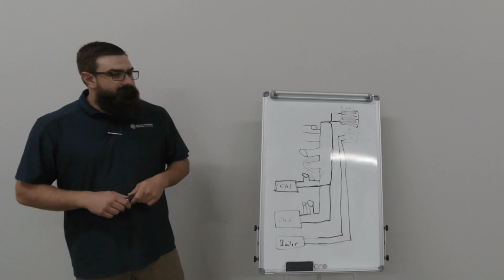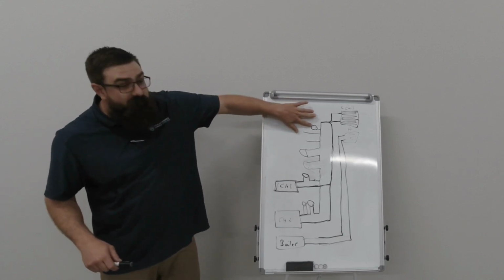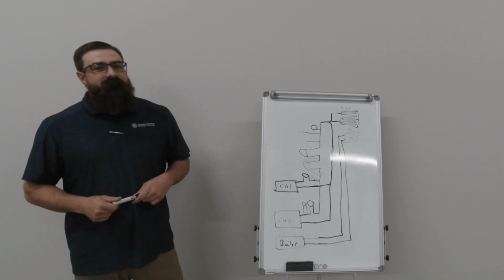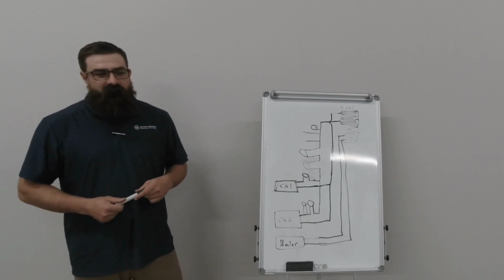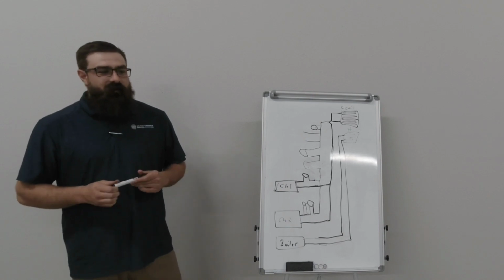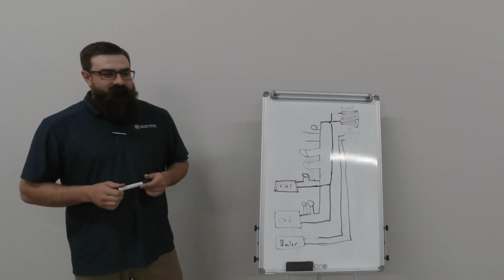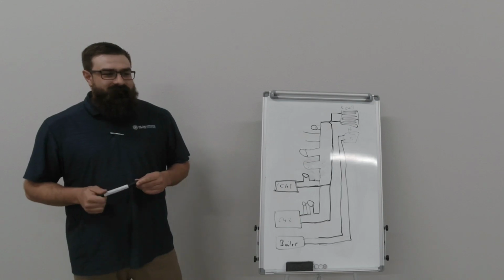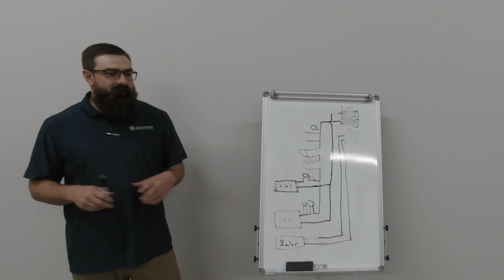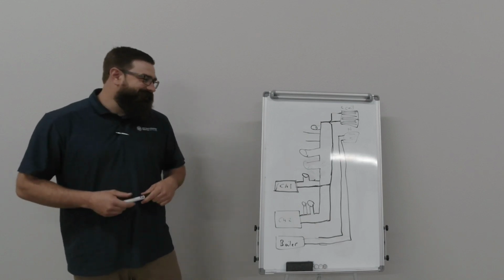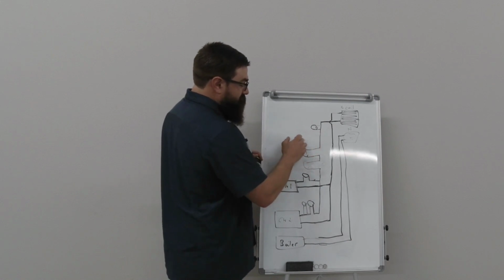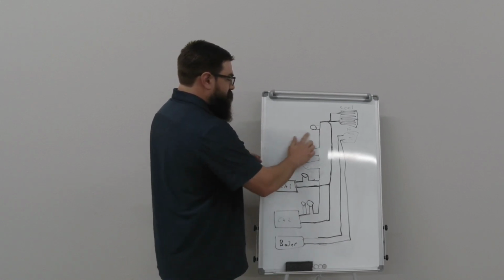Yeah, that's actually one of the buildings that I'm talking about. Oh yeah, I forgot we got that booster pump. But I did a 15-story downtown Houston, and they could not figure out why they were getting no flow up top. Had a new building engineer, hadn't been there for like 6 months. Nobody had been there longer than a year. Nobody knew about it. Pump was down. But I mean, they do have their purpose, especially in real high rises, not our little Austin stuff.